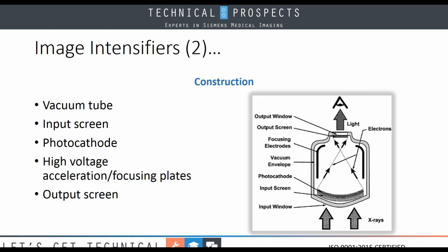But moving on, when we look at the construction of the image intensifier, you've got a great picture here that shows you the vacuum tube. It shows you the input screen at the very bottom where the x-rays come in, and we use the input screen, which is like a phosphorescent layer, that we take the phosphor and this converts the x-rays to light energy. This is then picked up by the photocathode, and the photocathode takes the light energy and converts it into electronic energy. The acceleration plates that you see along the side of the vacuum envelope, this here is what's going to accelerate our electrons, and they're going to blast the output screen at the very top. This screen should be much brighter than the input as it's condensed, smaller, and you now have the whole image placed at the very top of the intensifying screen.